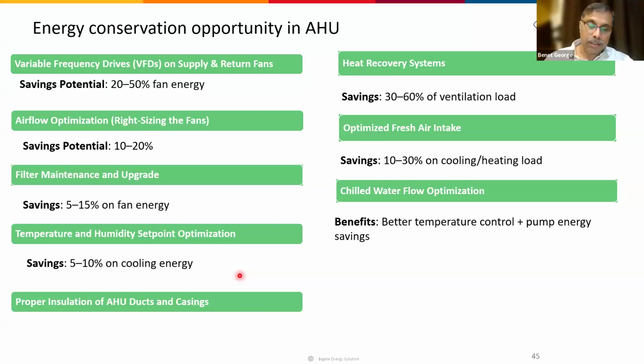In a space, some of the air has to be sent out, typically through the restrooms. So that much fresh air has to be added to the room. The outside air temperature is typically on the higher side, and the inside temperature is low. So we can recover the temperature from the exhaust air, and it can be used to pre-cool the fresh air. So that is called a heat recovery system.